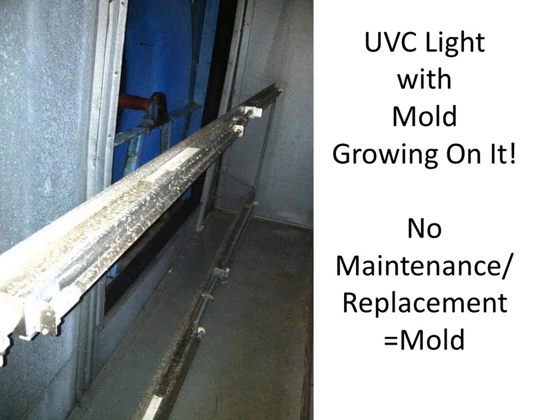And of course, if you don't maintain them, you could have mold growing on them. This is a picture of a UV light that's burnt out that has mold growing on it. But I'm sure that if you've been in the hospital industry or if you do work for hospitals, you see these quite often.